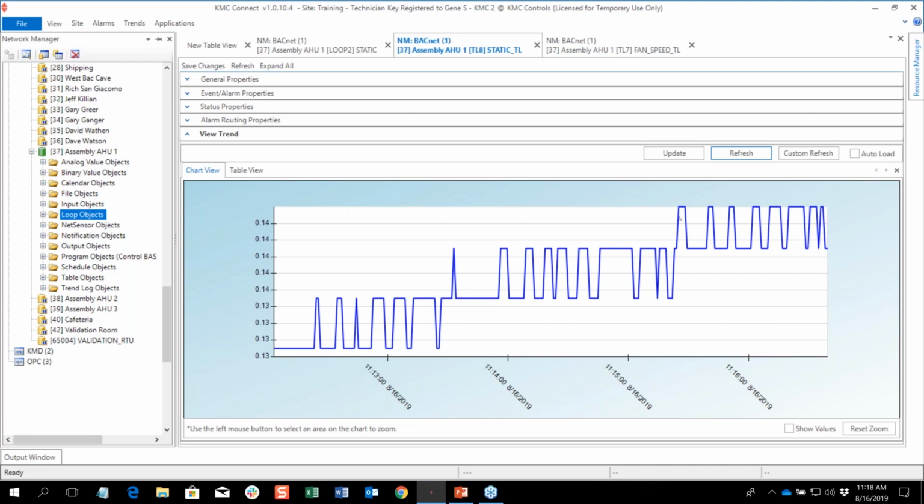Question came in about our static pressure example, and I'll throw this one out for Gene and Kevin too: in this sample, would this be a good situation where we could bring bias in to get that static pressure up to 0.18? Yeah, this would be a good example to get that right up there by just adding a little bit of biasing, and that would move it right up to 0.18. So I would also say that this could use some biasing that would give me the response, give me on setpoint faster.